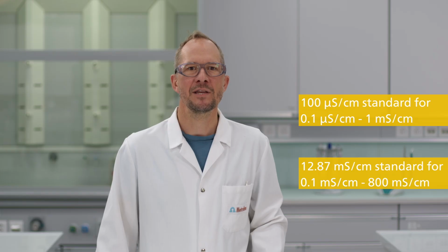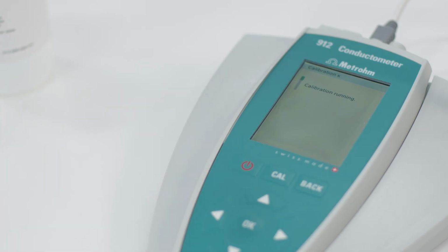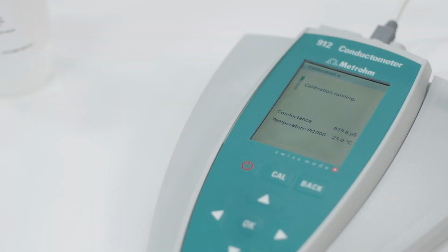It is not necessary to measure multiple standards for the calibration due to the large linear range of conductivity measuring cells. Simply choose a standard in the range of your expected sample conductivity. Confirm the entered values by pressing cal. The meter will measure the conductance and temperature of the standard solution. Accurate temperature measurement is critical for conductivity calibration. Your meter will indicate when the reading is stable and the calibration is accepted. It will then display the cell constant.